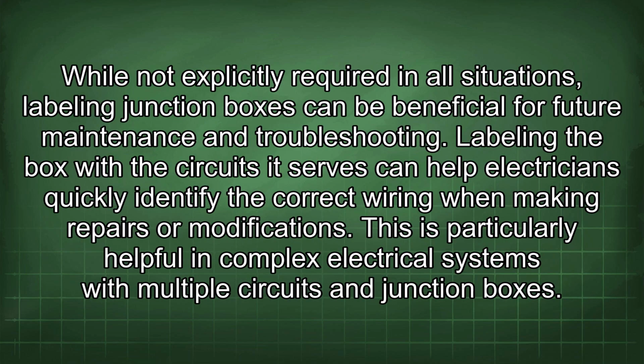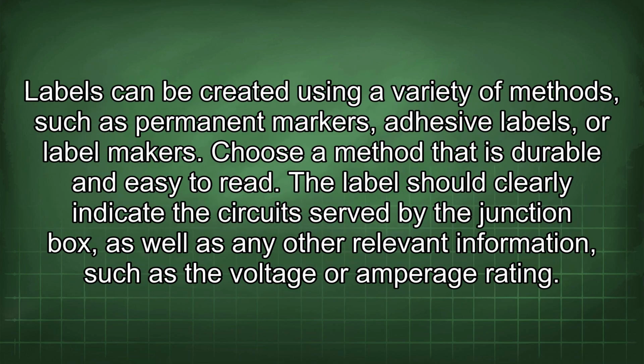While not explicitly required in all situations, labeling junction boxes can be beneficial for future maintenance and troubleshooting. Labeling the box with the circuits it serves can help electricians quickly identify the correct wiring when making repairs or modifications. This is particularly helpful in complex electrical systems with multiple circuits and junction boxes. Labels can be created using a variety of methods, such as permanent markers, adhesive labels, or label makers. Choose a method that is durable and easy to read. The label should clearly indicate the circuit served by the junction box, as well as any other relevant information, such as the voltage or amperage rating.